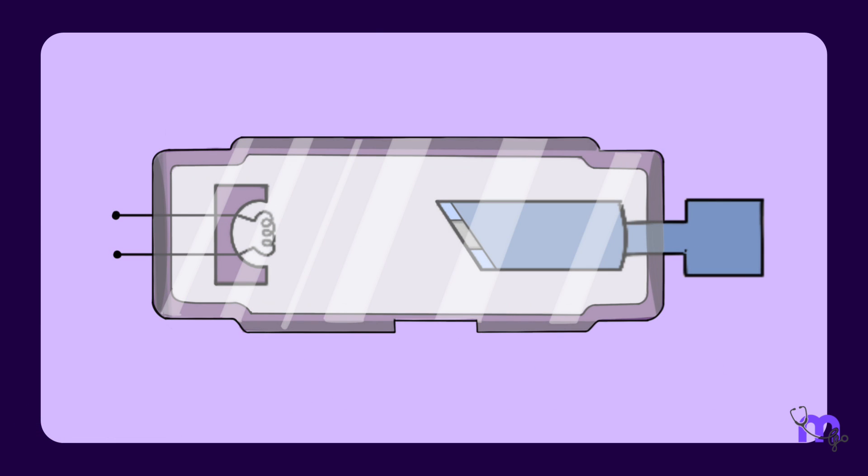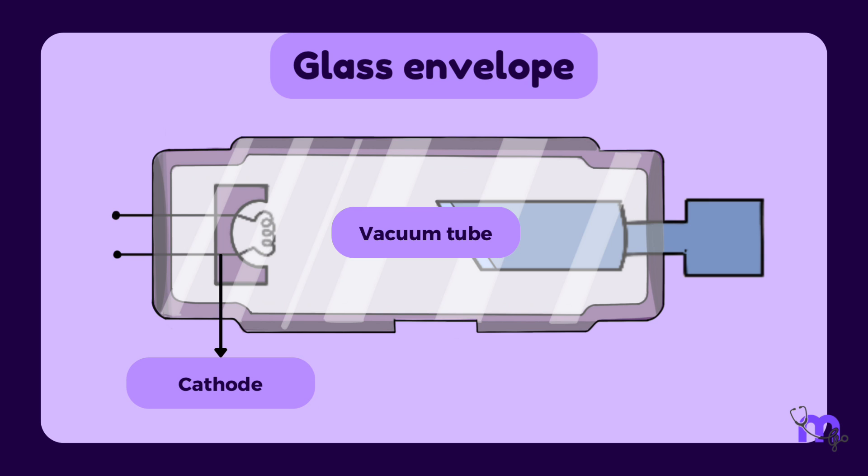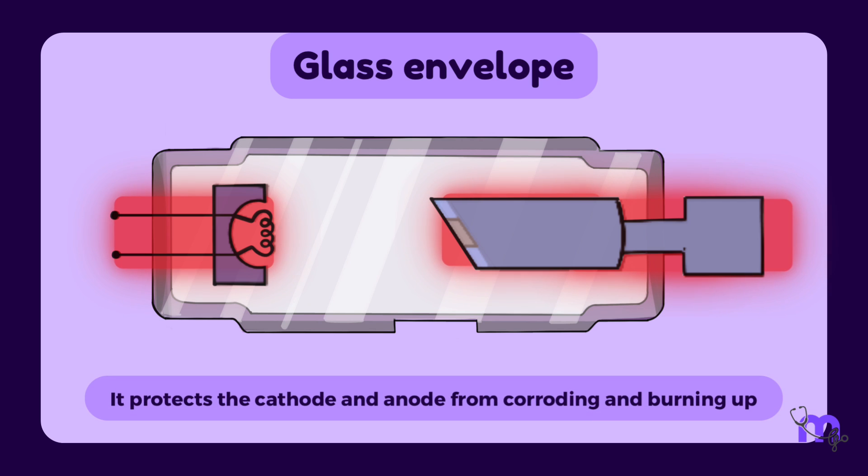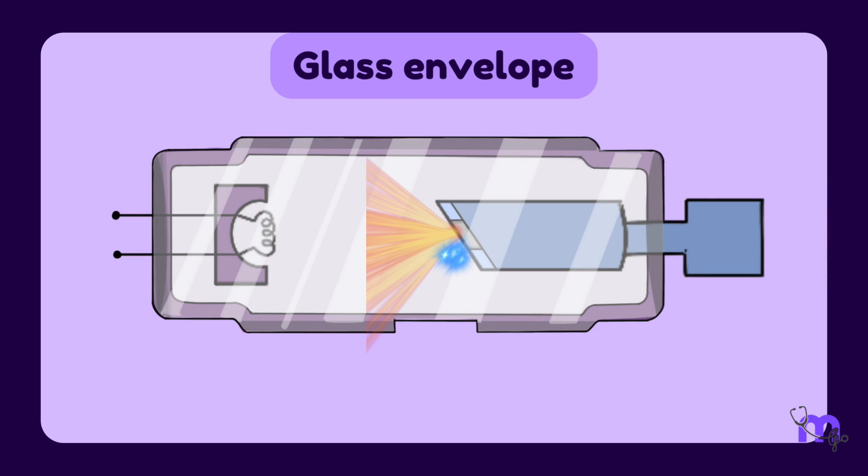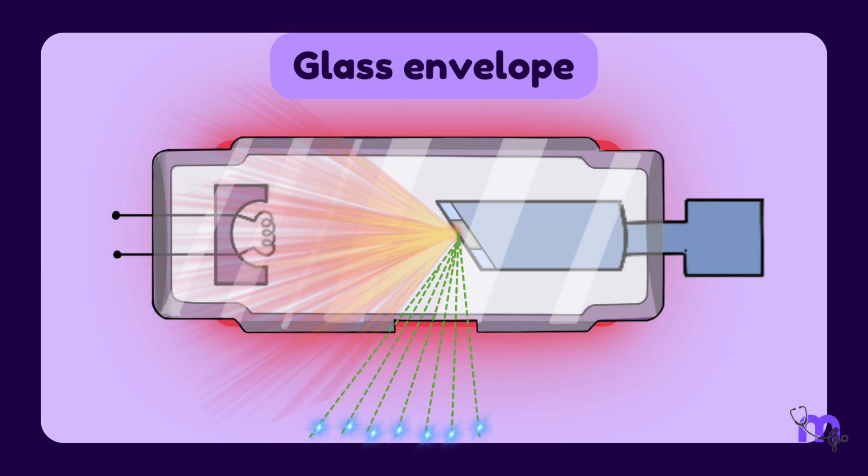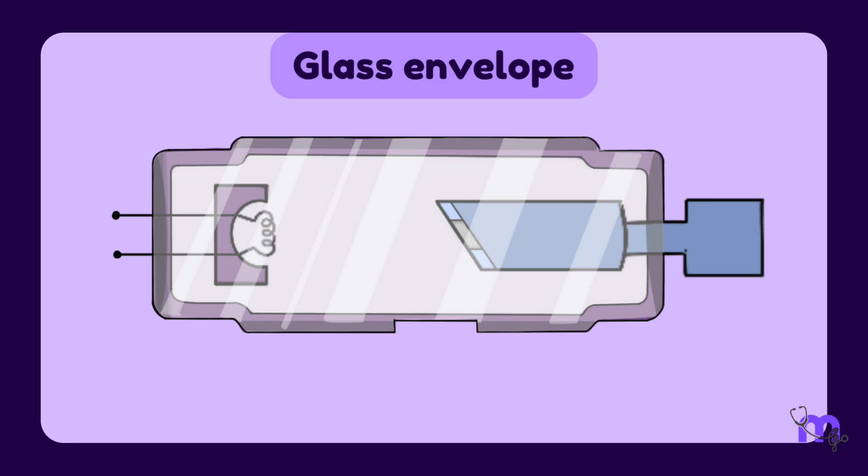The glass envelope is a vacuum tube that encases the cathode and the anode. It protects these elements from corroding and burning up when producing X-rays. The glass envelope heats up significantly, therefore it is made of a unique heat-tolerant material known as borosilicate glass, also known as Pyrex glass. The central area of the glass tube has a window through which the X-rays come out.